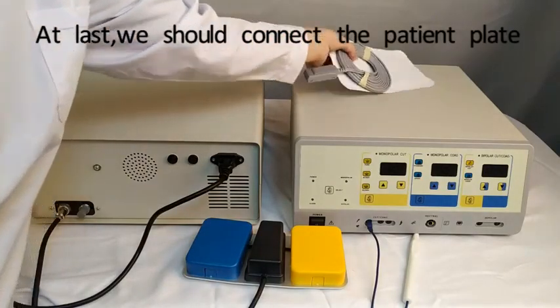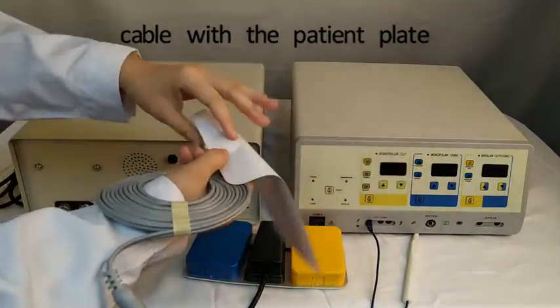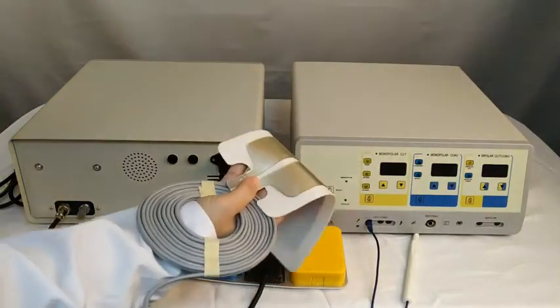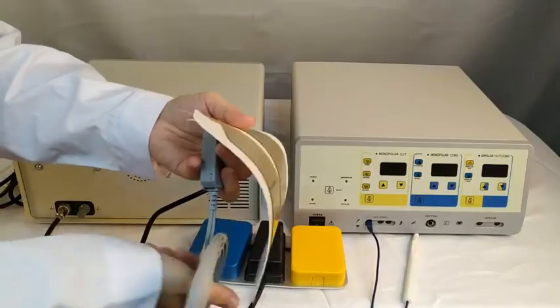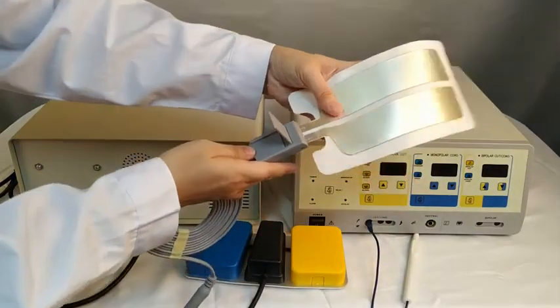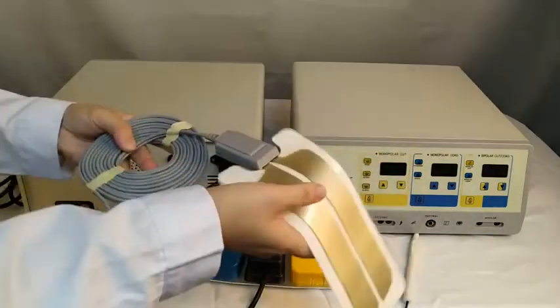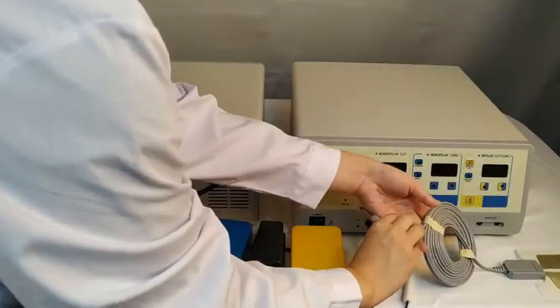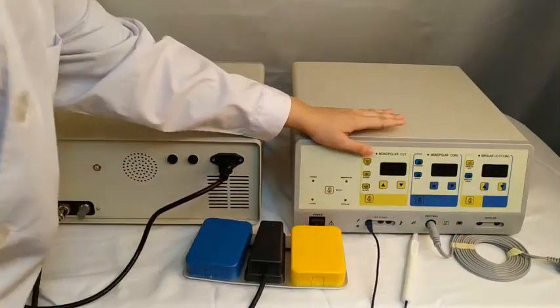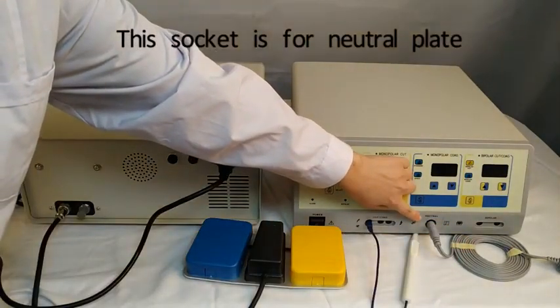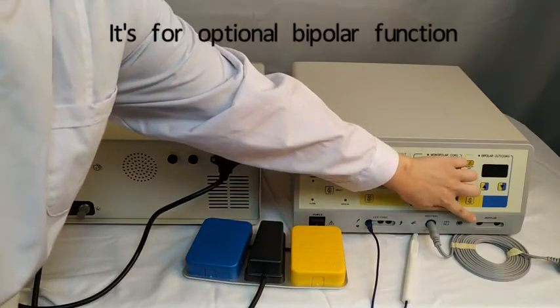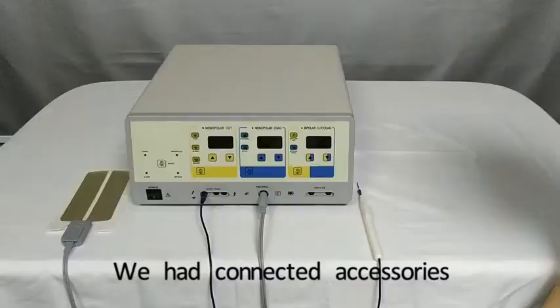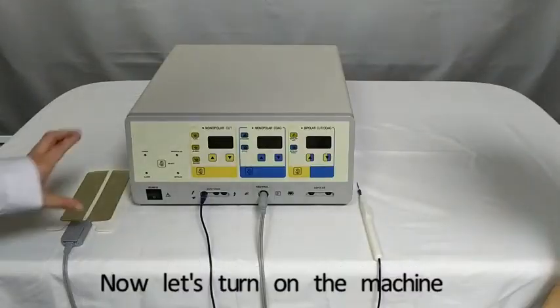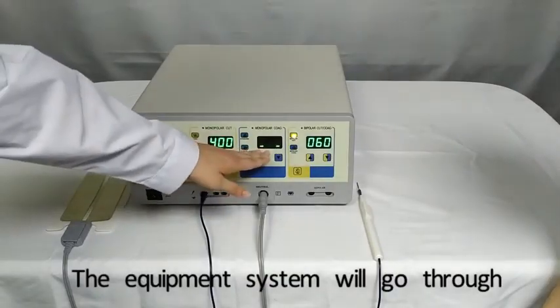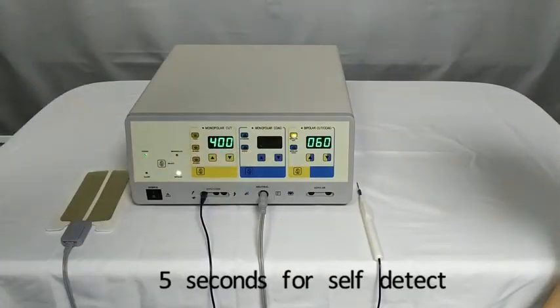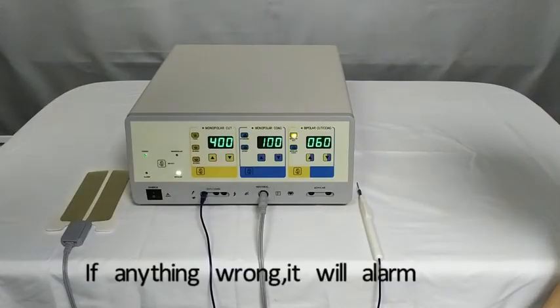At last, we should connect the patient plate cable with the patient plate and put it into this socket. This socket is for the neutral plate, and the socket beside it is for the optional bipolar function. We have connected the accessories. Now let's turn on the machine. The equipment system will go through 5 seconds of self-detect. If anything is wrong, it will alarm.